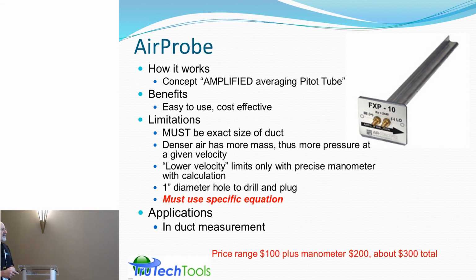The air probe is an amplified averaging pitot tube. Those are also passed around. They had multiple points, multiple holes in them. These are designed to be sensors to put in a variable air volume system to go back through a control system to feed back airflow in a branch run. They must be the exact size of the duct. You can't use one that just fits. It can't be sticking out. It can't be too short. It has to go across the full duct to get the correct measurement from it.